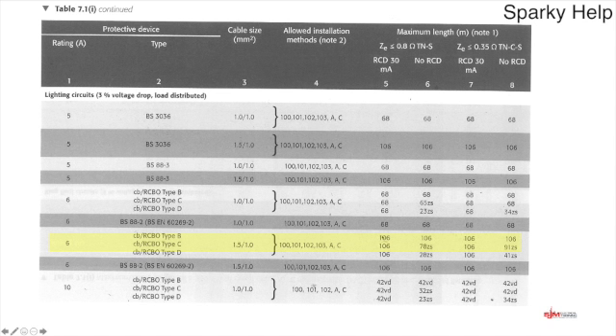Moving on down, that will have 106 meters, and this is the maximum length of run for this cable. If you install 106 meters or less, and providing the load is distributed evenly for this particular cable, you will meet all requirements. It only comes into a bit of a problem if you start looking across here, if you go to a type C breaker, and then with no RCD the maximum length of run now is 78 meters. You'll notice it says Zs after it, because basically what that means is the maximum Zs for this protective device would fail if you went longer than 78 meters. In other words, the ohmic value, the resistance, is too high.